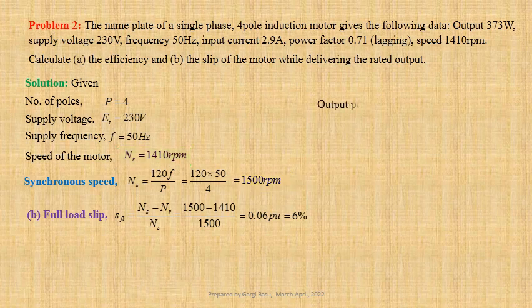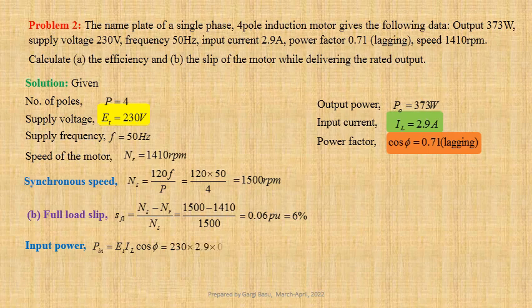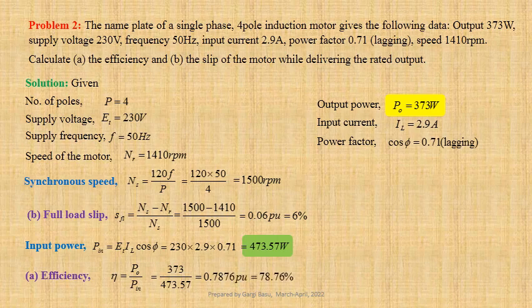Given output power P equals to 373 watts. Input current Il equals to 2.9 ampere. And power factor cos phi equals to 0.71 lagging. For single phase induction motor, input power Pin equals to Et into Il cos phi. Using values we get 230 into 2.9 into 0.71, that gives us 473.57 watt. Efficiency of the motor eta equals to Po divided by Pin. Using values we get 373 divided by 473.57, that gives us 0.7876 per unit or 78.76 per cent.